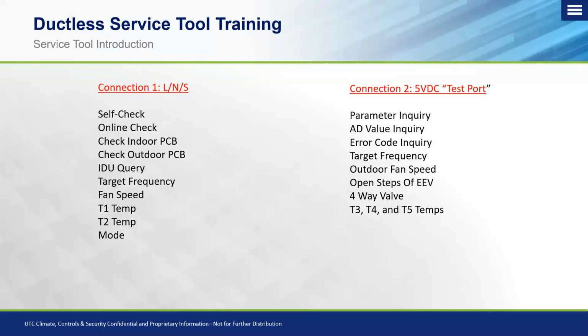From there, with the L, N, and S connection, you have access to self-checks, online checks. You can check an indoor PCB, an outdoor PCB for any issues. You get an indoor unit query: a target frequency, a fan speed, a T1 temperature, T2 temperature, and the mode. And that's all in the indoor unit. Now, of course, T1 and T2 are going to be in the indoor unit. You can wire this up to check an outdoor PCB, and we'll get into the different features and how you can actually set those up and run those checks to confirm if you actually do have a bad board or if there's another factor at play.